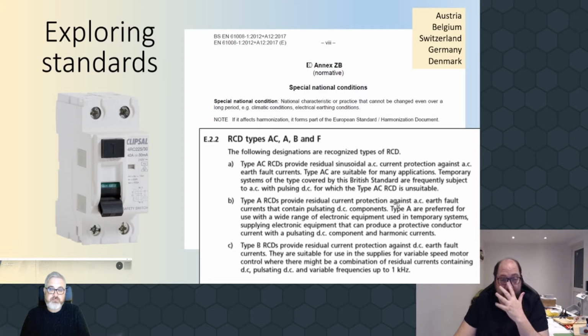This is something we've had to take on board, because we test and install with lots of distribution equipment, and most manufacturers of distribution equipment for a number of years just threw in the cheaper RCBOs, which would be AC. There are a couple that would go ahead and put the Type A, but it took a lot of to and fro, and even today some of the big ones will just throw in Type AC because there's a lot of ignorance in testing in that area.